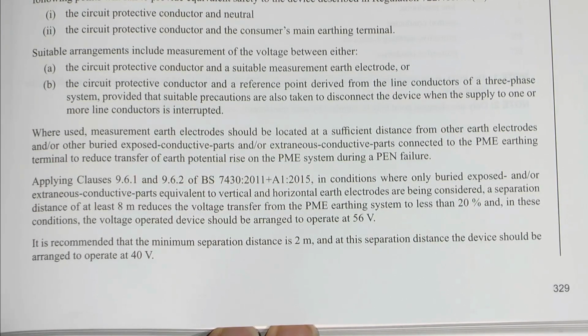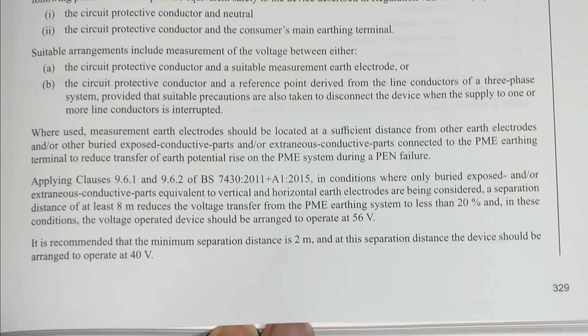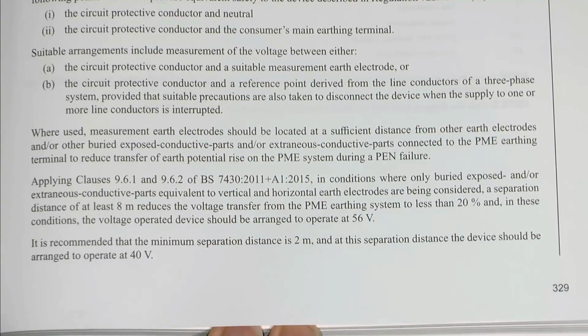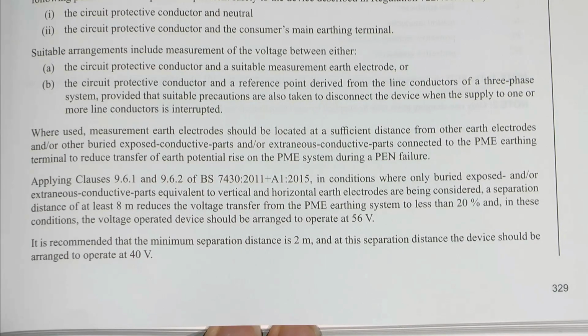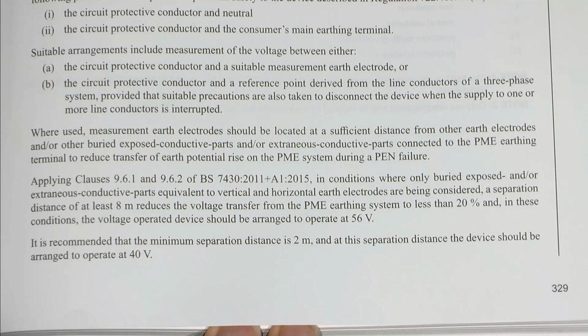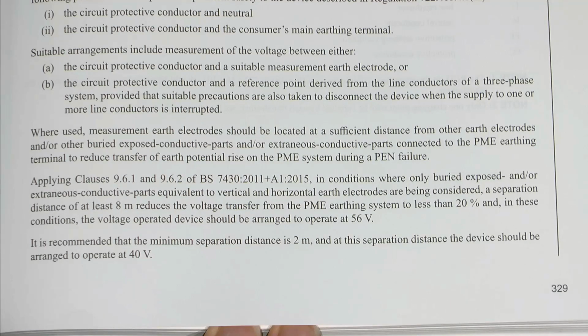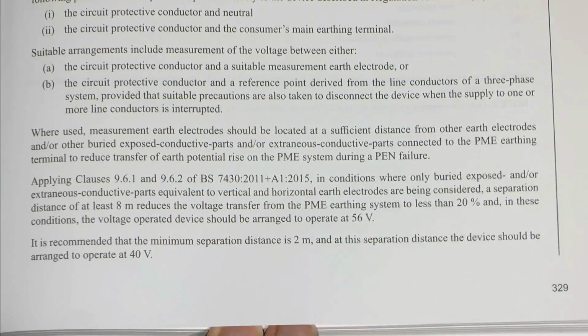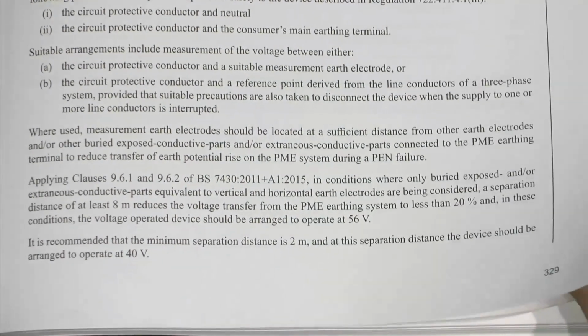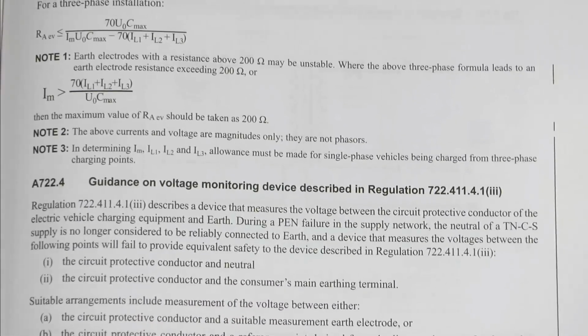It's not something which many manufacturers have implemented in their devices. There's at least one which has. But again, this is going to be quite a difficult thing to do. You've got to get that electrode pretty far away from anything else that happens to be in the ground there connected to the system. And in many cases, it's simply not going to be possible to use it. But if you do want to use it, then guidance is provided there.